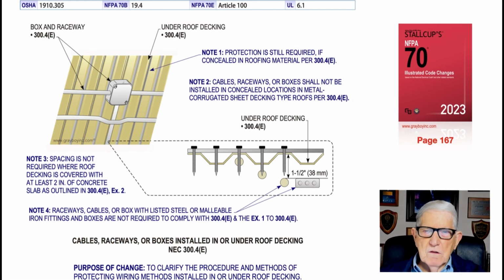Now this illustration deals with cables, raceways, or boxes installed in or under a roof decking. I think note 3 is the first thing that's important to look at, but mainly the purpose of the change was to clarify the clearance rules of a box being set underneath a flat roof area. But notice note 3 now says that the spacing is not required where the roof decking is covered with at least 2 inches of concrete slab, as outlined in 300.4(E) exception number 2.